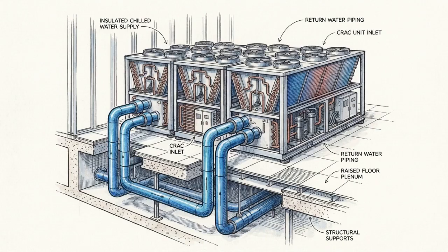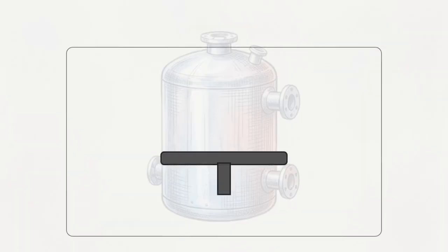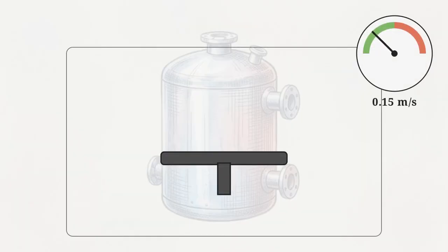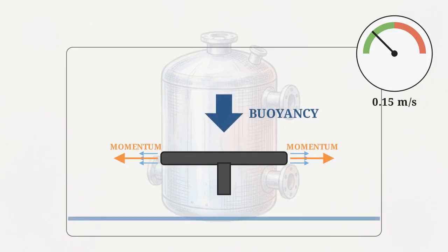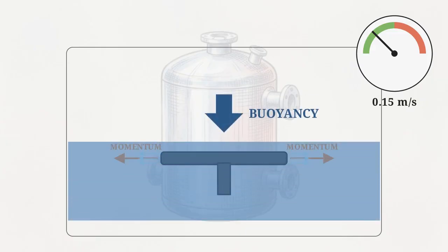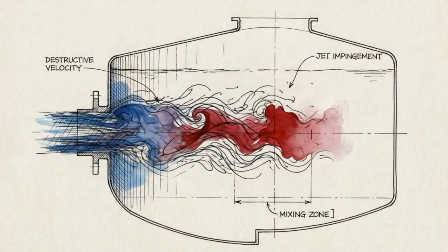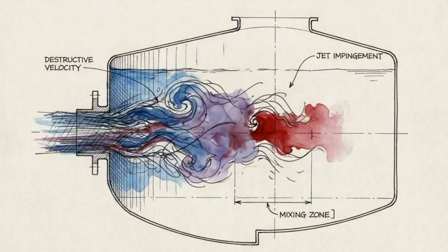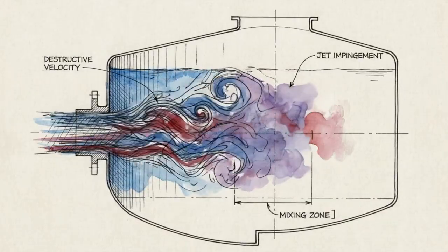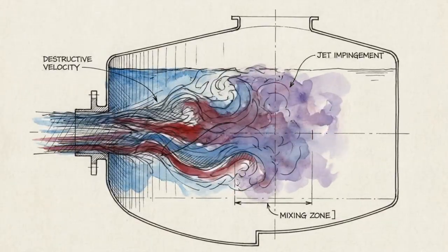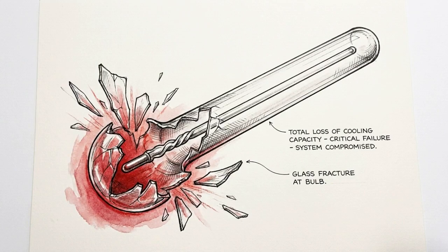The space taken up by the diffusers and the thickness of that thermocline restrict exactly how much cold water is available to the servers. To preserve these layers, engineers restrict the water velocity at the diffusers to strictly under 0.15 meters per second. This low velocity ensures buoyancy forces dominate over momentum. If the velocity exceeds that limit, jet impingement occurs. The fast-moving water destroys the stratification, violently mixing the hot and cold layers and instantly ruining the tank's cooling capacity.